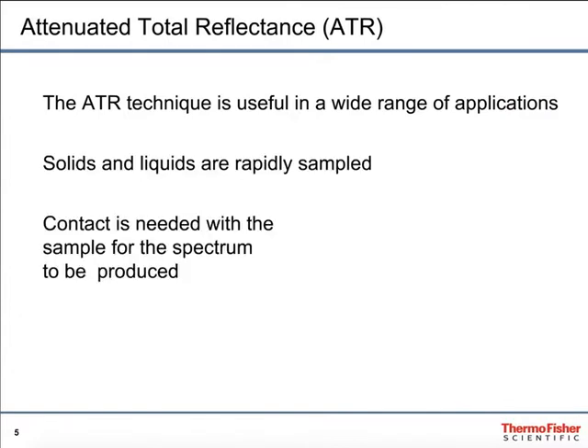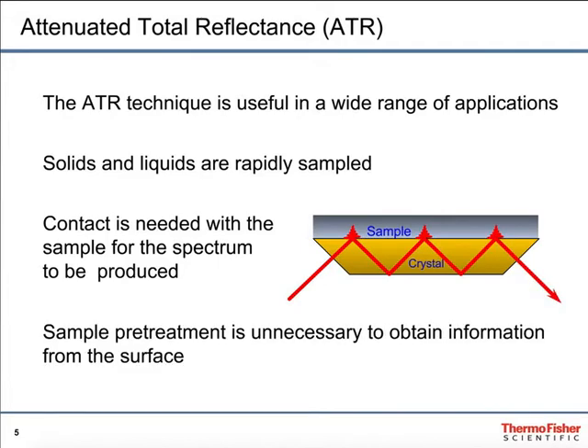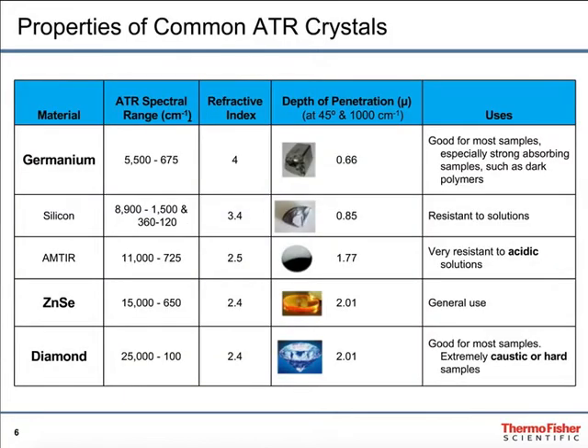Attenuated total reflection, or ATR, has grown to become the most popular technique currently used in infrared. Solids and liquids can be very easily analyzed. The critical thing here is that the sample must be in contact with the active surface of the crystal, where the IR beam interacts with it. Sample pre-treatment is usually not needed — whether it's a powder, a liquid, or a gel, you can get good contact with the surface and do ATR. At the heart of the ATR technique is the crystal.